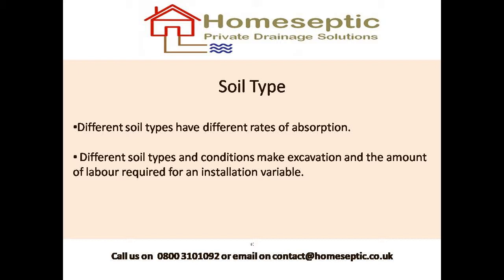Maybe look to undertake a percolation test on your soil, which is basically dig a hole a metre by a metre, then dig a further hole at the bottom of about 300 millimetres and measure how long it takes water to dissipate from that secondary hole. There's instructions on our website on how to do it, or just give us a shout and we can tell you how to do that.